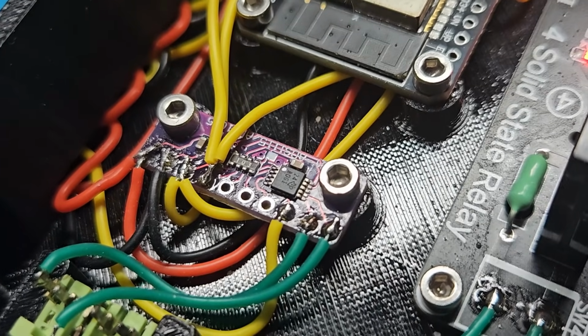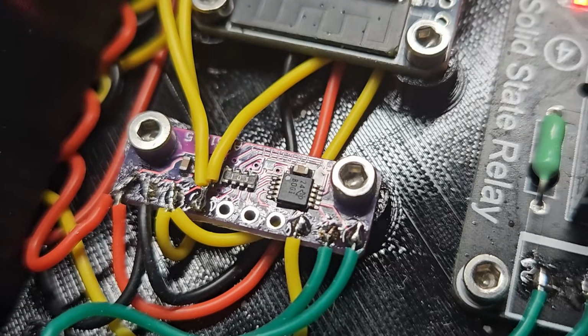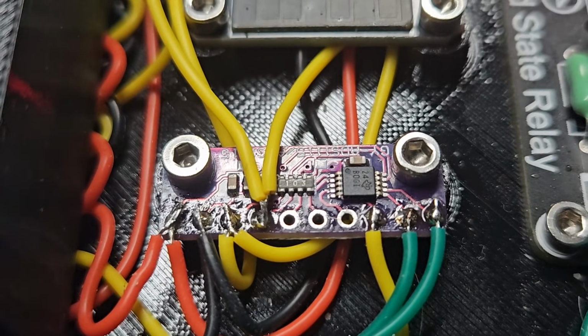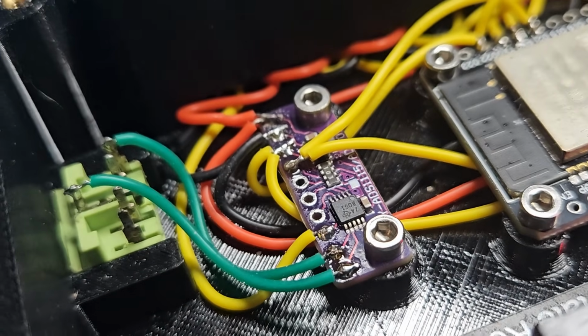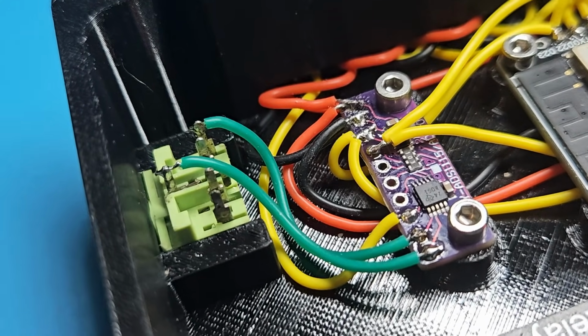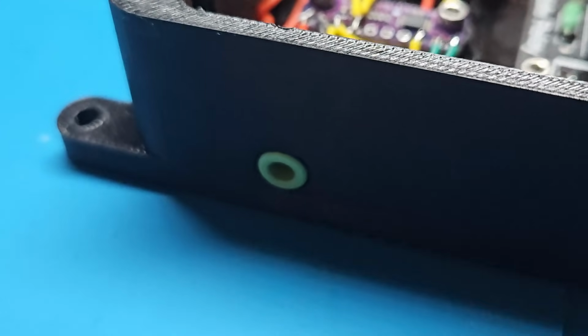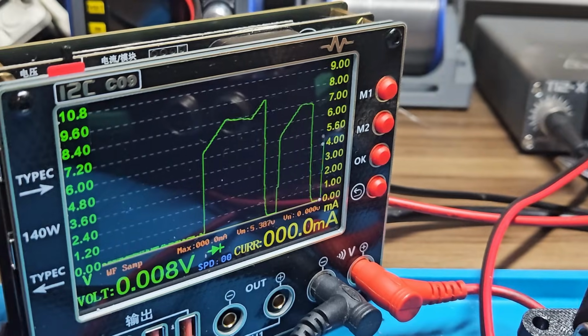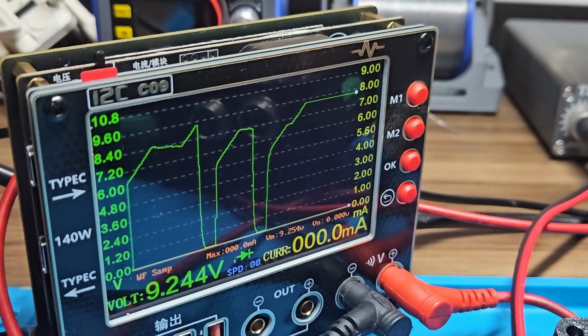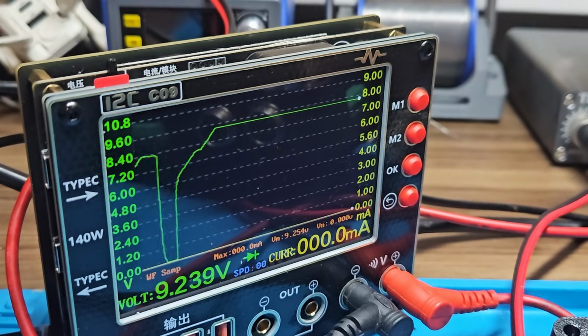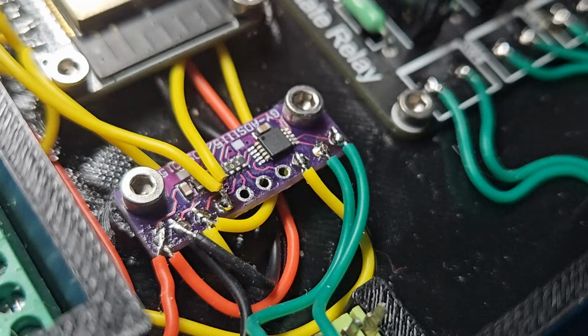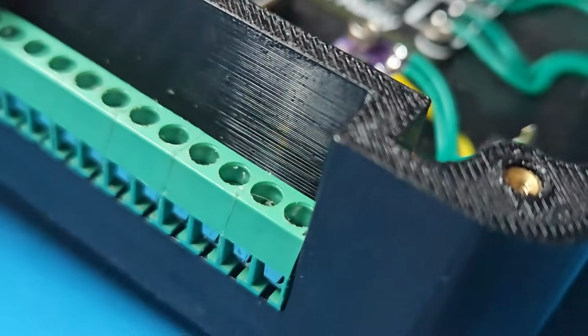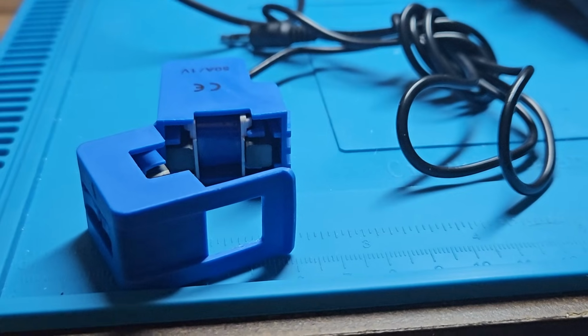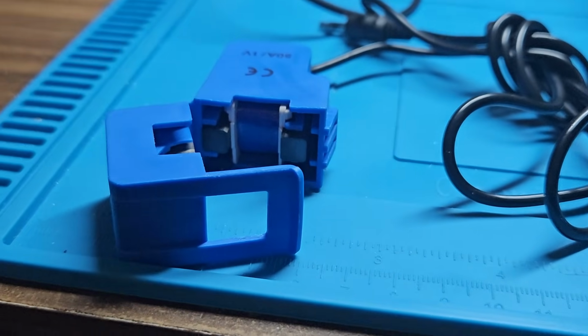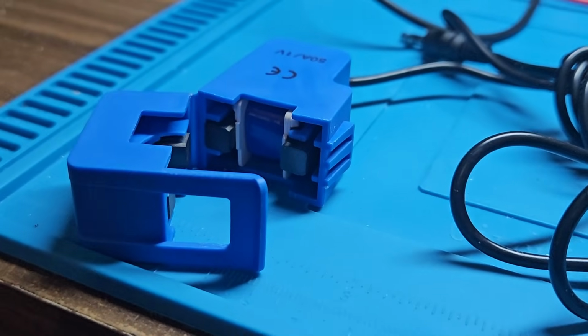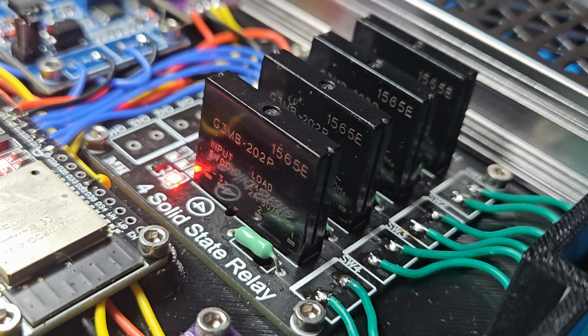The next active component in line is the ADS1115, a 4-channel analog to digital converter. It's also powered with 3.3 volts and uses I2C to communicate with the ESP. I know the ESP itself has many analog to digital converters, but they're heavily dependent on the input voltage, as their reference voltage is directly tied to it. The ADS module, on the other hand, has its own internal reference voltage, which provides very high stability and thus very accurate readings. I'm using this component to read the voltage from the external pressure sensor, which reads the pressure in the entire system, and for the SCT013, a current transformer responsible for reading the AC current the VFD uses. Now let's jump to output modules.